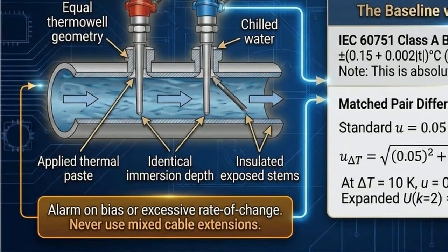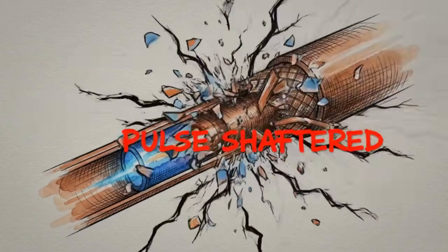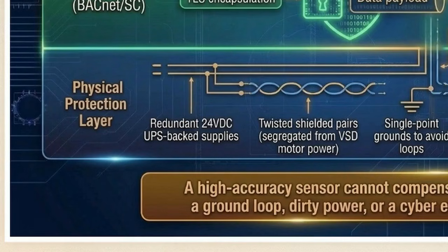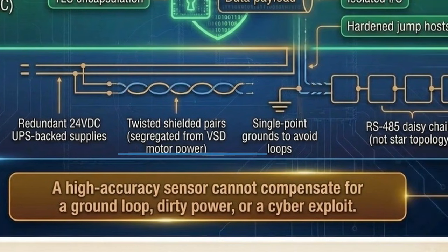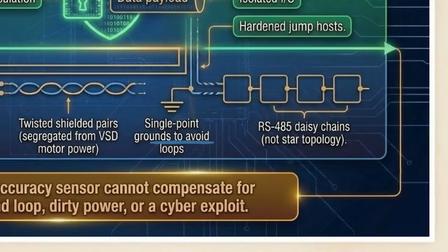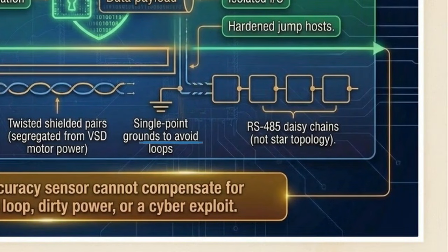We now move to Layer 2. The precision generated by these physical devices is highly fragile and easily destroyed by electrical and cyber interference. This diagram outlines the instrument power and cabling requirements. The physical protection layer dictates redundant, UPS-backed 24-volt DC power supplies and twisted shielded pairs, strictly segregated from heavy motor power. It requires single-point grounds to eliminate loops that distort sensitive analog signals across the daisy chain.